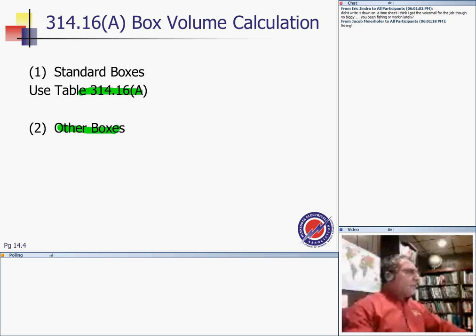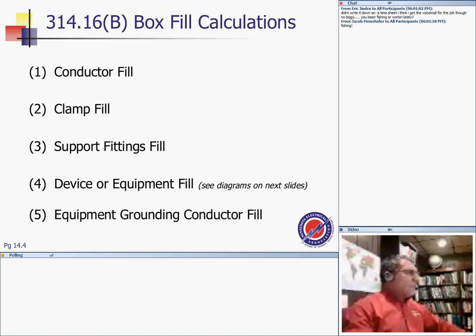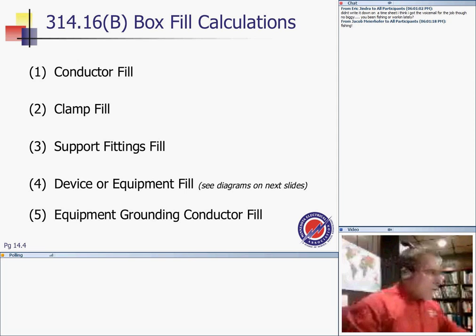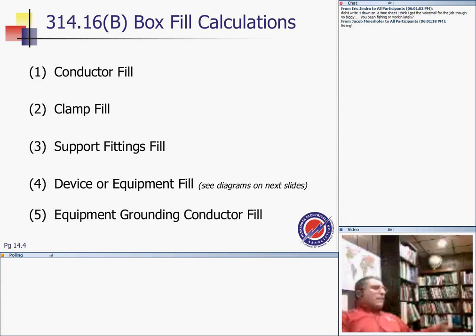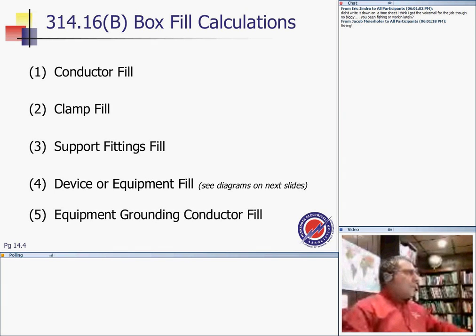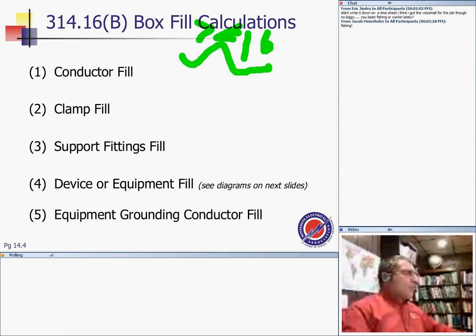Okay, so moving on. These tables, we have to use them. Now it becomes what counts and what doesn't count. Conductor fill, what counts, guys? Every conductor counts as one. If you have a conductor that loops more than 12 inches inside the box, more than 12 inches, the conductor counts as 2.